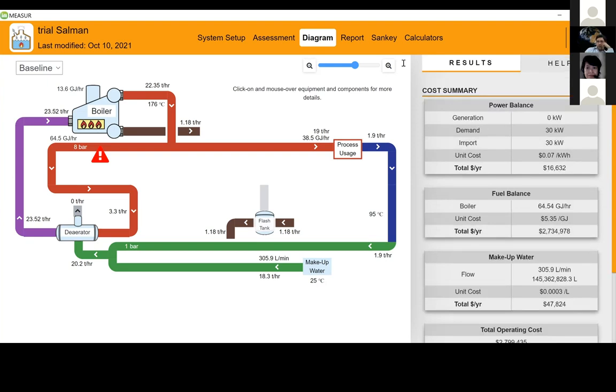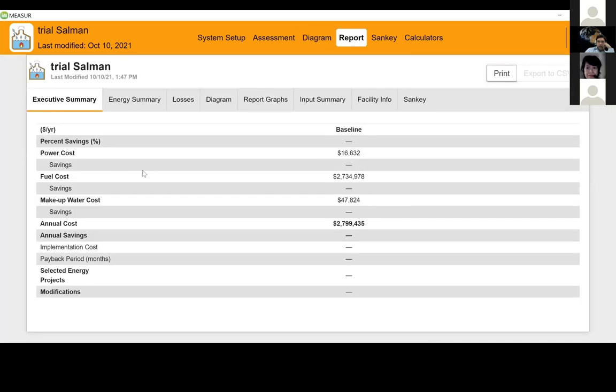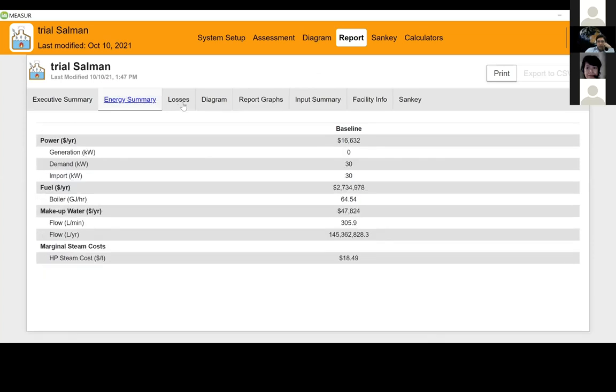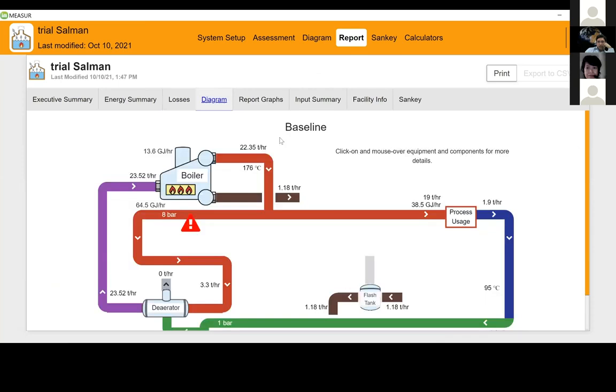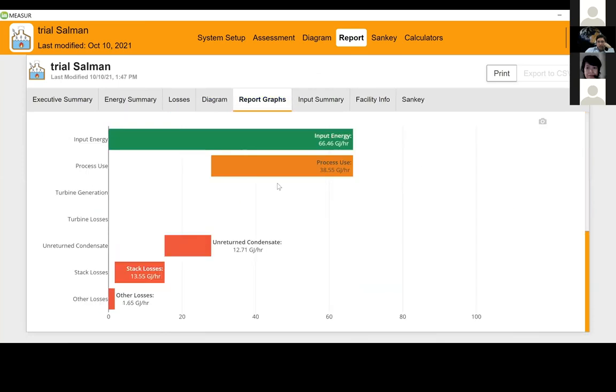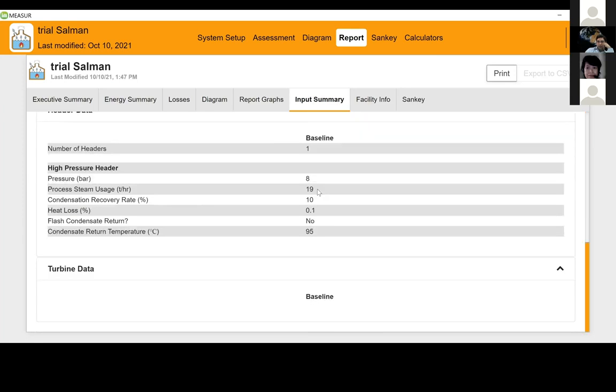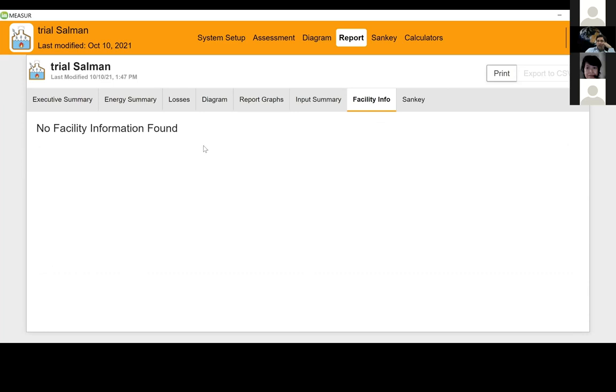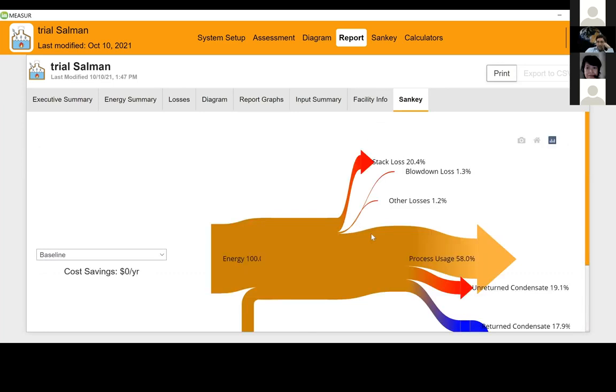Based on this, we can go to report. In the report section, we have the values in terms of percentages and amounts. We have an executive summary, we have losses calculated, we have the diagram. Report has certain graphs also there. So out of total input energy, how much is being used in process, how much goes into unreturned condensate, how much goes into stack losses, and how much goes into other losses. So these are the saving opportunities that we have here, which can be recovered. Then the input summary, what was the data provided inside, some facility info which we did not provide in this case, and a Sankey diagram.